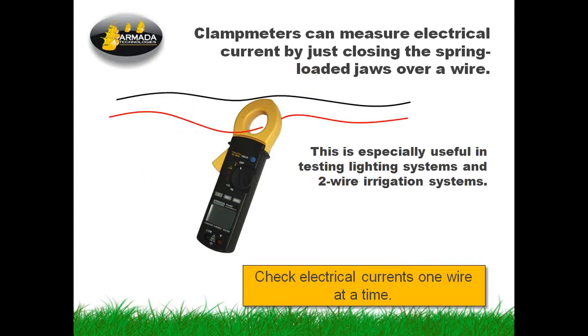One point about the clamp meters is if you're measuring current, you can't clamp around the entire cable in the system you're working with. For example, if you've got a heavy 12-gauge cord going out to the field for a lighting system, you need to split the cord apart and measure the current in one wire. So you clamp over one wire and read it that way. If you clamp over the whole thing, you won't read. You'll read zero current. Won't be accurate.